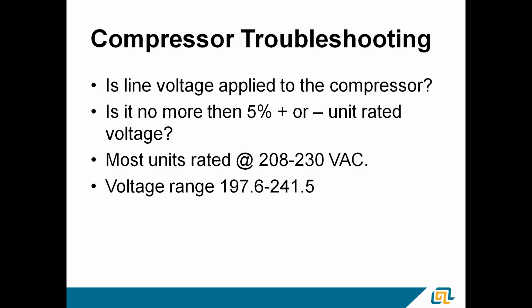The big one here is that 197 volts. If you're down below 198, 197 volts, especially when that compressor is trying to start, you're definitely going to have some issues starting. It's not going to start reliably. It's probably going to take out starting components and capacitors.